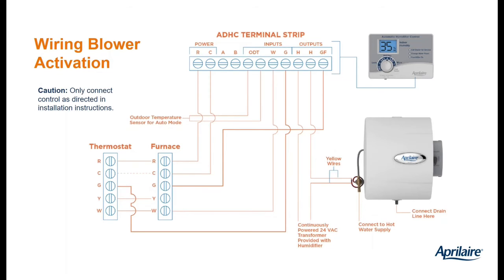Then at the top of this diagram, the 12 o'clock position, you can see there are the screw head terminals inside of our automatic humidistat. And then you've got the humidifier itself. In this case, it's a bypass humidifier with the solenoid valve and the 2 yellow wires coming off of it. And at the very bottom of the diagram, you can see where the 24-volt transformer would wire in. So let's just go through it. This is very, very straightforward. Let's start at the left.